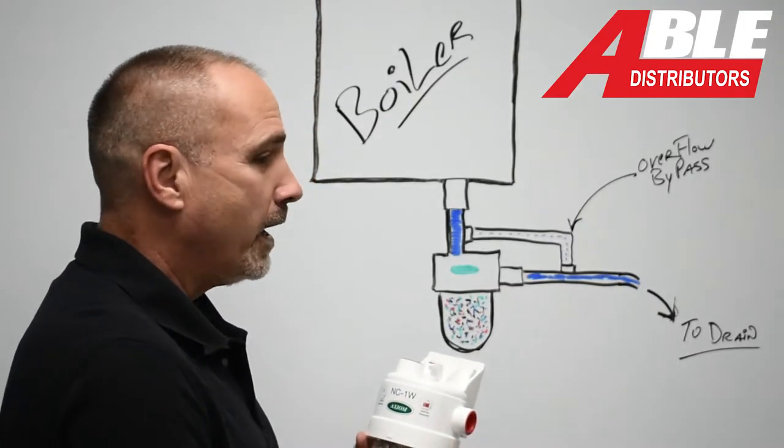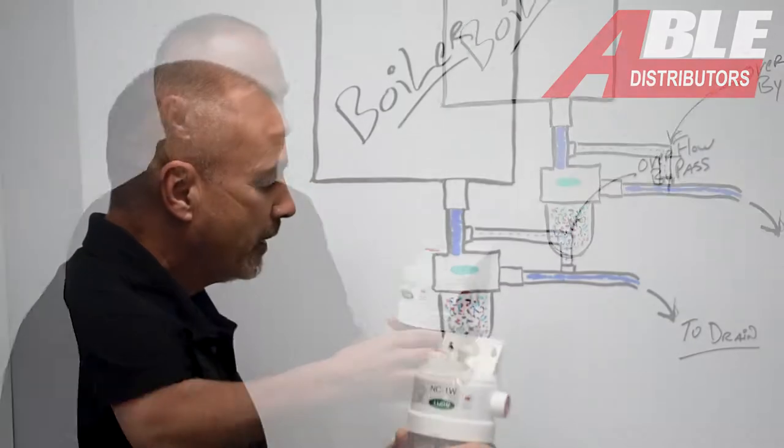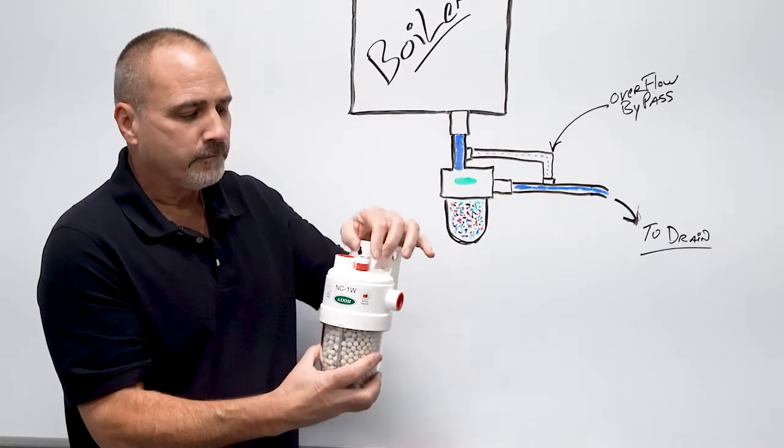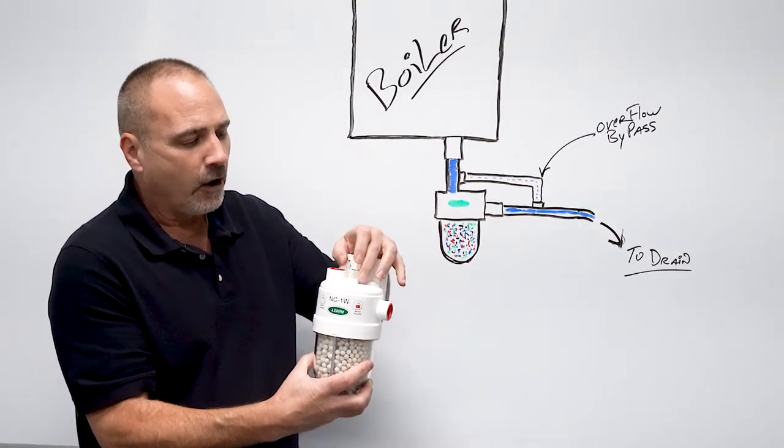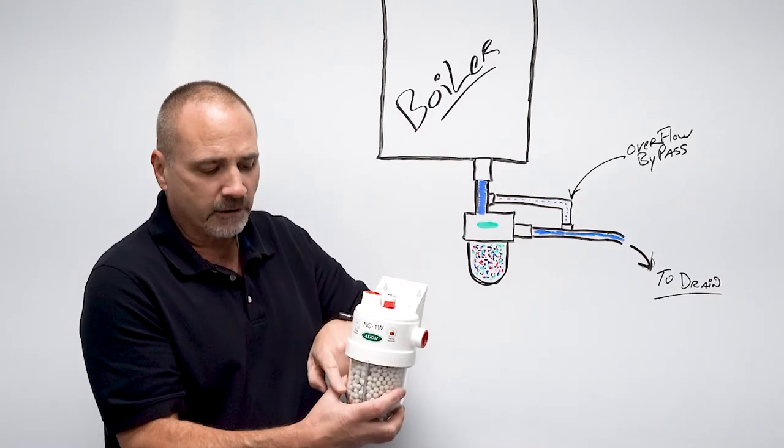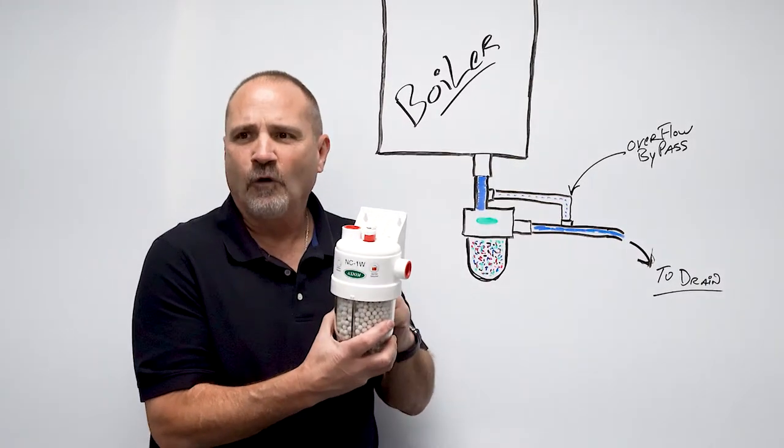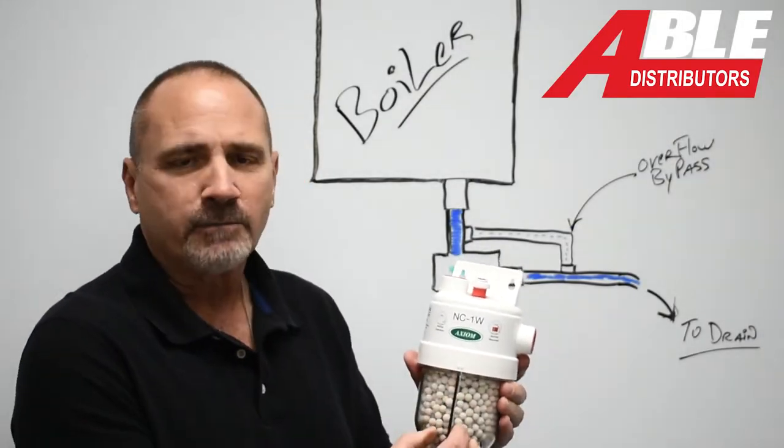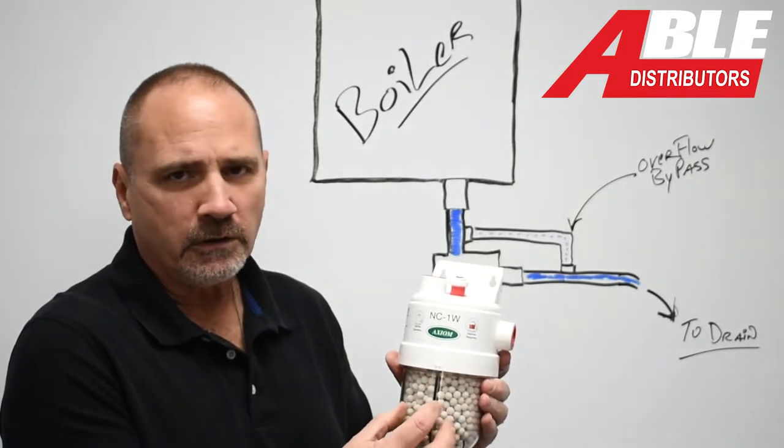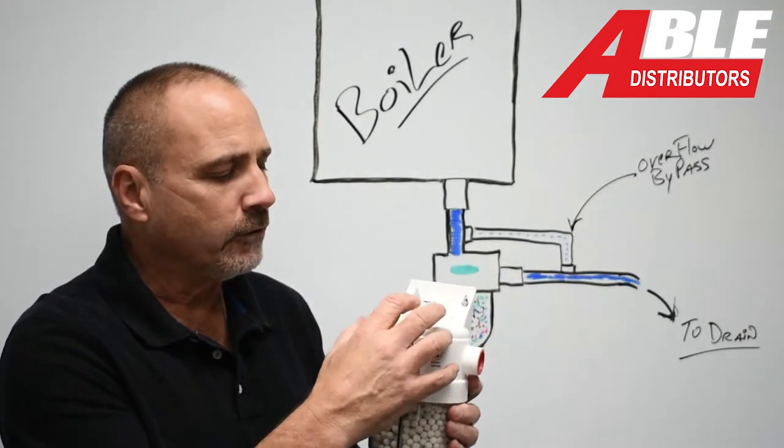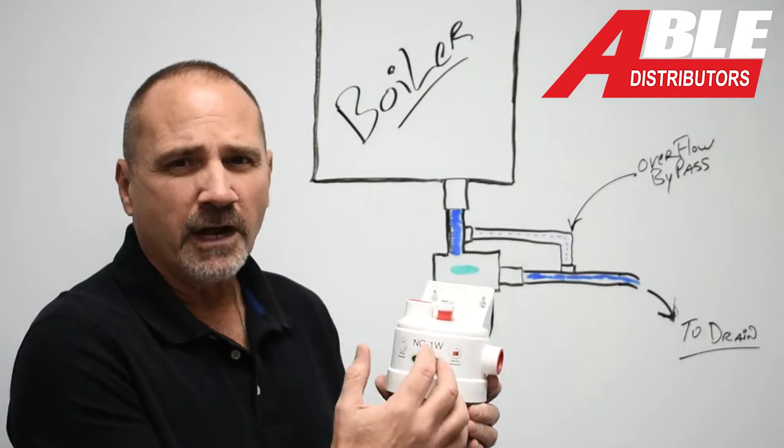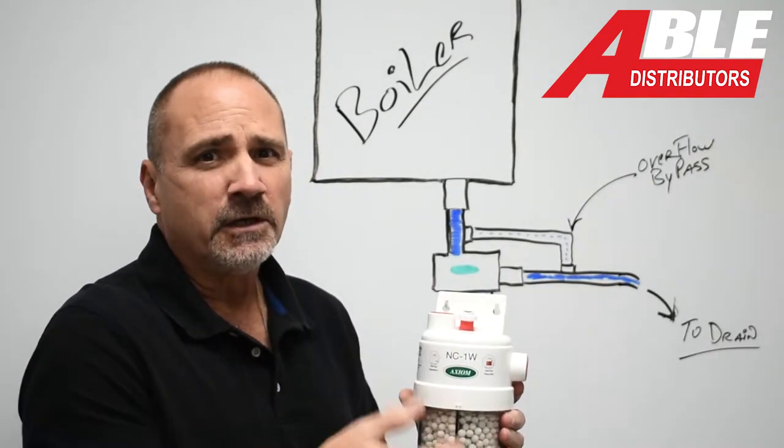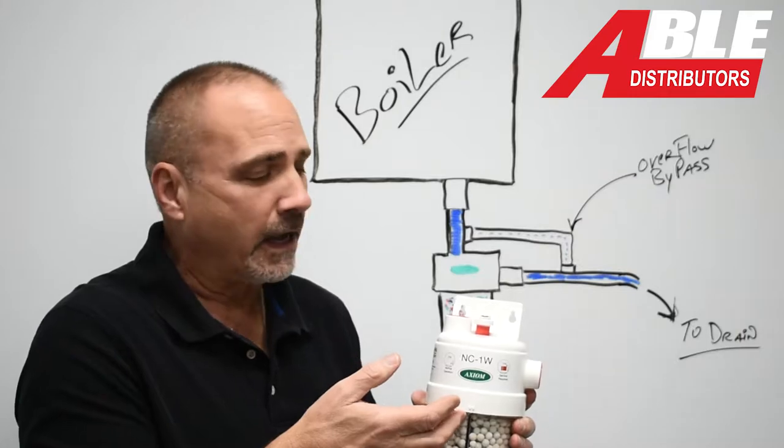This does have a little pop-up float, and all that does is let you know that something happened, that this thing got full at one point, whether it got plugged up or these deteriorated enough and wasn't letting water flow through. It just lets you know that on your next checkup, if you see this is up, you know at one point the water level got high.